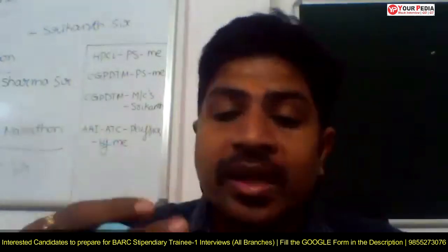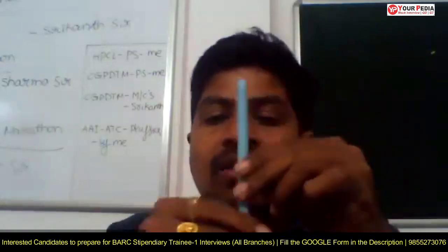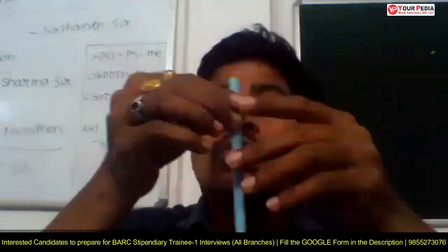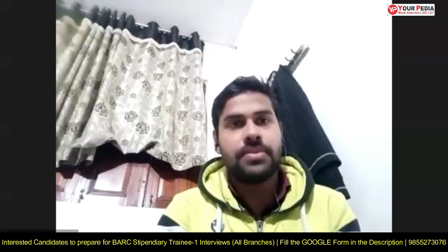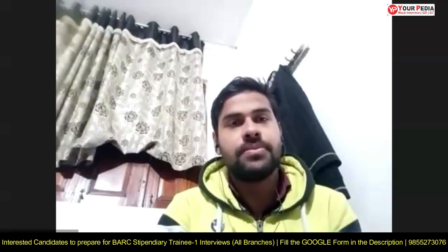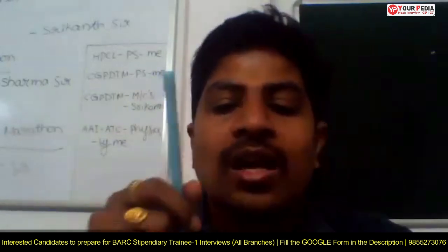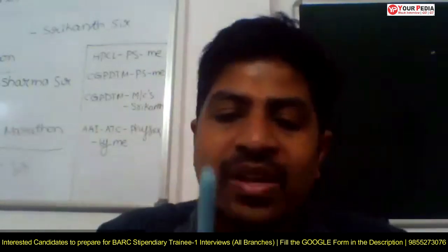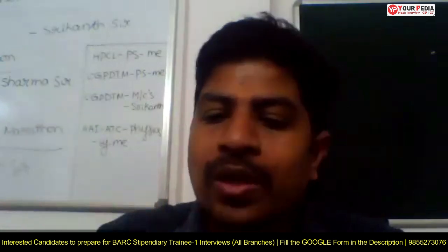If I'm going for unsymmetrical configuration on a single tower, this side circuit A, this side circuit B, two circuits I can send at a time on a single tower. That's why we're going for three-phase unsymmetrical or asymmetrical configuration. But this unsymmetrical configuration is causing my system to be unbalanced. Why? Because GMDs are not equal. If GMDs are not equal, inductance and capacitance per phase are not going to be equal. Therefore, my system is going to become unbalanced.